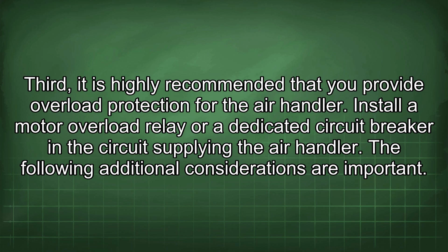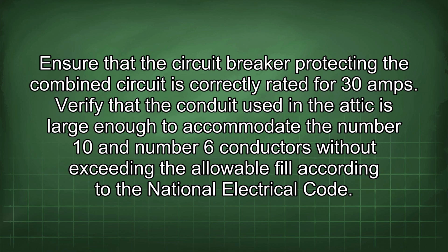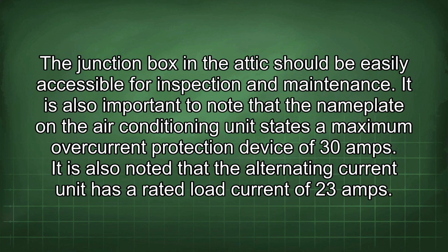The following additional considerations are important. Ensure that the circuit breaker protecting the combined circuit is correctly rated for 30 amps. Verify that the conduit used in the attic is large enough to accommodate the number 10 and number 6 conductors without exceeding the allowable fill according to the National Electrical Code. The junction box in the attic should be easily accessible for inspection and maintenance.